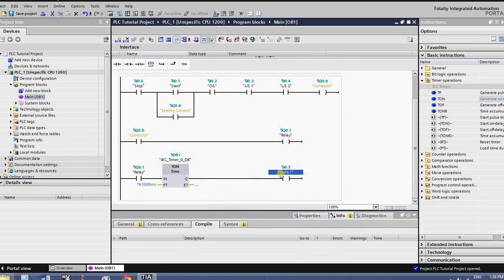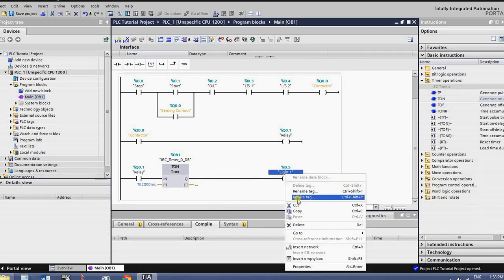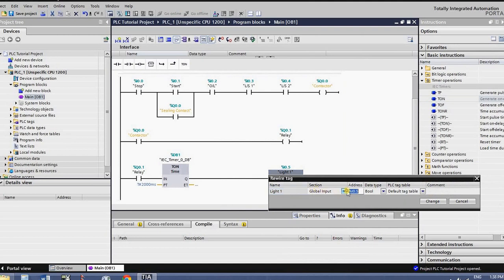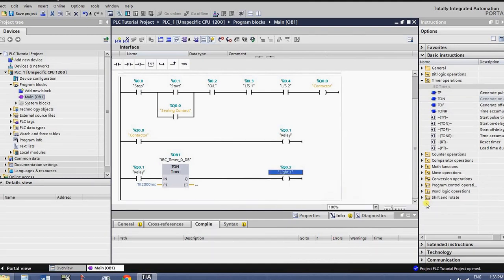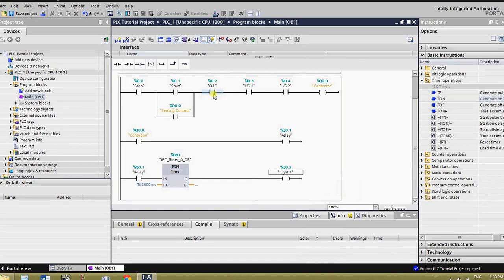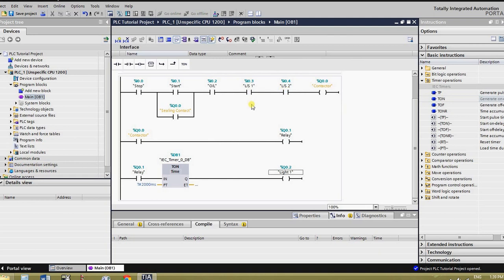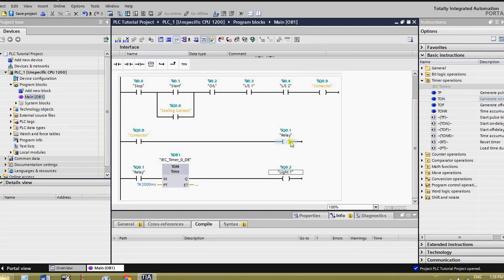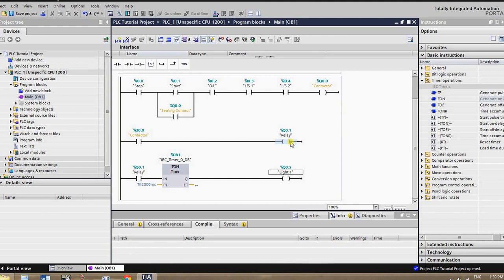That should be an output, a global output. So the way you would hook this up is just like you did your start stop before. Your thermal overload on your contactor, the output side of it will go into your 0.2 at the top of your PLC, your switches will go to 3 and 4 at the top of the PLC. You're also going to pull a wire for the relay from 0.1 on the bottom of the PLC over to the hot side of the relay, and then you're going to run your neutral back to your terminal strip. You're going to do the same for your light, except it's going to come out of 0.2 on the bottom of your PLC.